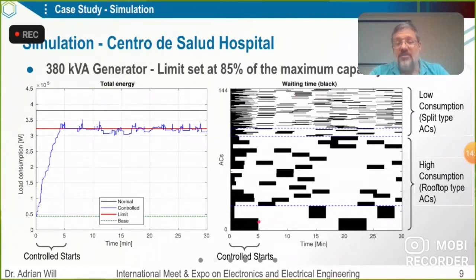The black parts are stops, the white parts are starts. You see there are only short stops, 3 to 5 minutes, distributed along the 30 minutes in this case, and we achieve the blue line. The red line is 85%, the black one is 100%. As you can see, the air conditioners start in a sequential fashion, so you don't overwhelm the generator and make sure you don't have an outage. That's the main problem — the air conditioners going all at once and provoking an outage.